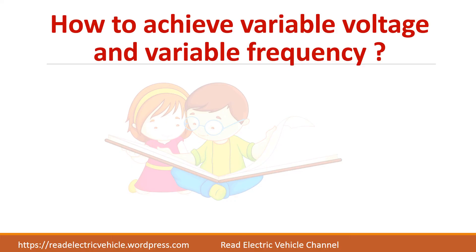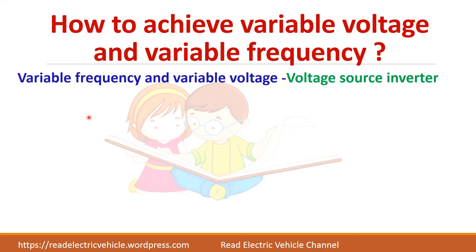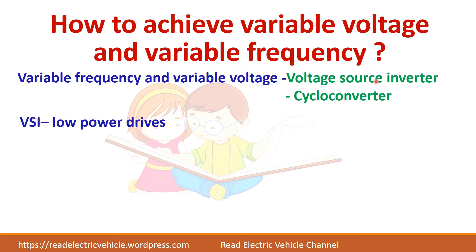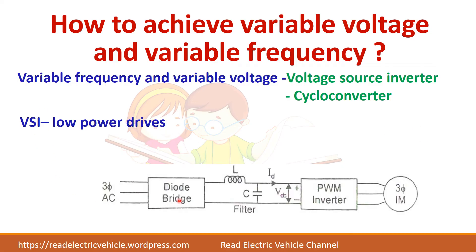To achieve variable voltage and variable frequency, you can use a voltage source inverter to change both voltage and frequency, or a cycloconverter. For a three-phase induction motor, a three-phase PWM inverter can be used. By changing the voltage and frequency of the inverter output, you can keep the V by F ratio constant. The inverter requires a DC supply from a diode bridge rectifier.